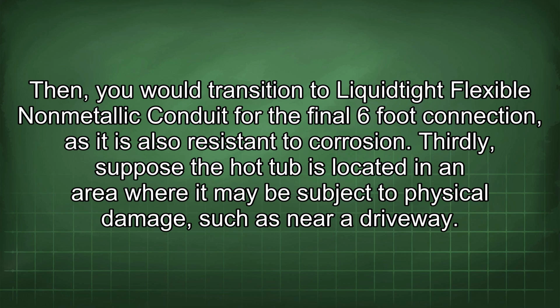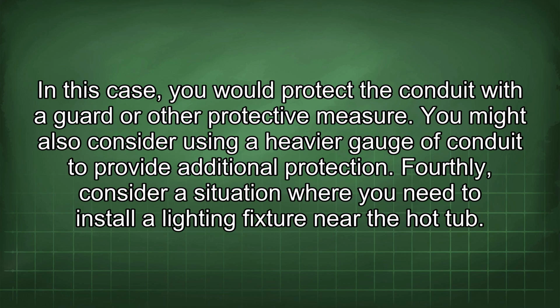to corrosion. Thirdly, suppose the hot tub is located in an area where it may be subject to physical damage, such as near a driveway. In this case, you would protect the conduit with a guard or other protective measure. You might also consider using a heavier gauge of conduit to provide additional protection.